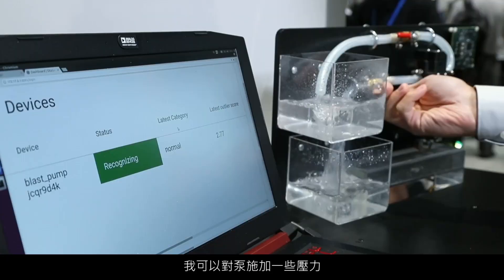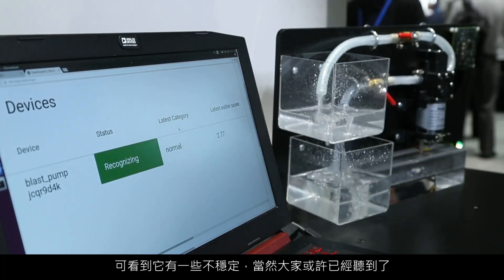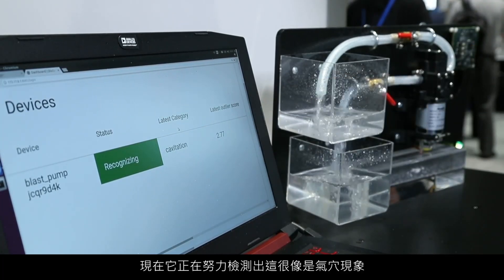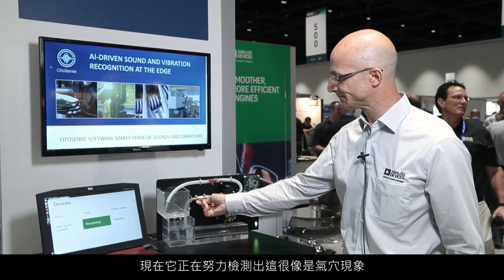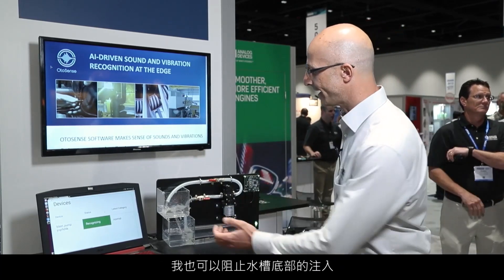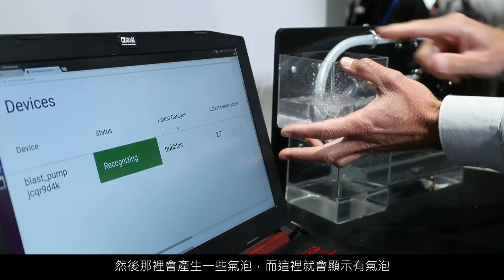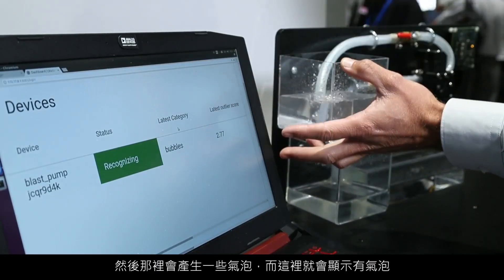I can create some stress on the pump, and I have some instability, and of course you can maybe hear it — it's right now struggling with this close to cavitation behavior. I can also prevent the bottom of the tank from filling, and then we'll have some bubbles in there, and we'll say bubbles here.